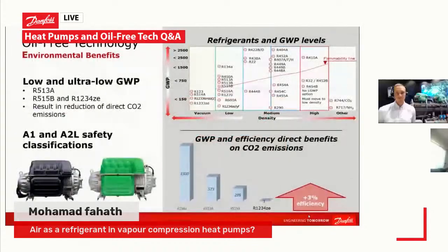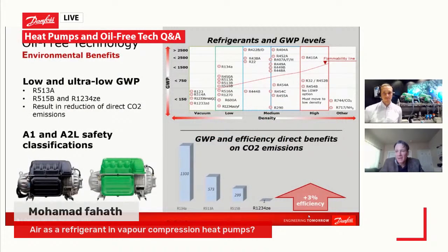So air as a refrigerant is a higher pressure refrigerant. A CO2 based refrigerant Turbocor compressor could be designed, but it's not going to be more efficient than the positive displacement alternative you can use for it as well. That's why we're focusing on lower density solutions for a turbo, variable speed, oil-free, multi-stage turbo-based compressor, or any turbodynamic compressor device, to be more efficient than a positive displacement. It really needs to operate with lower pressure fluids. So we can do an air or CO2 based compressor design, but it's not going to be more efficient than the positive displacement alternative. So it's not likely that we will pursue that.